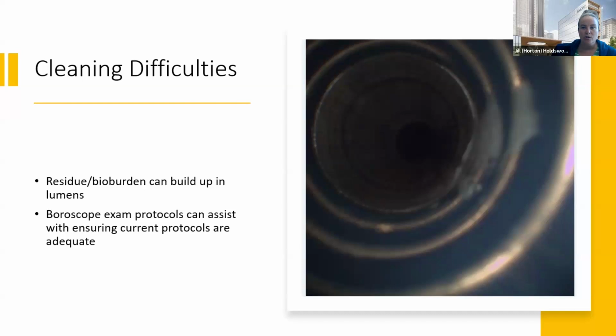So how did we find something like this? We have to use a borescope to find something like this. So if you're not using borescopes, it's a good idea to start using borescopes. Otherwise, you're not going to know what's lurking inside these lumens. You have to have a plan on how often you're going to use them, when you're going to use it, and making sure that you're going back and re-cleaning afterwards. But you also have to have a plan for what happens when I see something. When you see something like this, you can't say, okay, there it is, send it on through, because we can't see something like this and just keep using it.